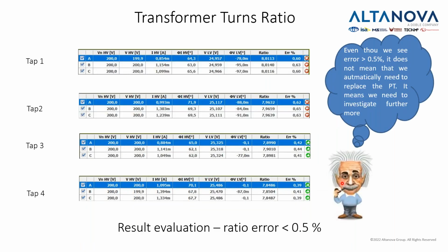What is important to mention, and this is generally a rule when we come to transformer testing, I will mention some numbers today, like 0.5%, 2%, 3%, 1%. If we are slightly above this number, it doesn't mean that we need to change that transformer right away. What we need to do is follow that parameter, maybe do tests more often, and definitely do more tests. So this transformer doesn't need to be changed, because we see that on some positions of the tap changer we have some issues, but other positions show us good results.